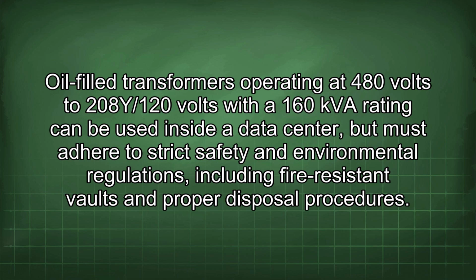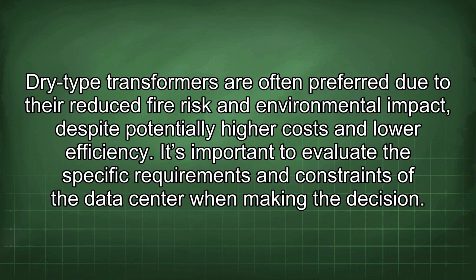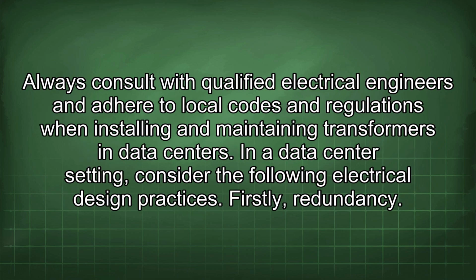Oil-filled transformers operating at 480 volts to 208Y/120 volts with a 160 kVA rating can be used inside a data center, but must adhere to strict safety and environmental regulations, including fire-resistant vaults and proper disposal procedures. Dry-type transformers are often preferred due to their reduced fire risk and environmental impact, despite potentially higher costs and lower efficiency. It's important to evaluate the specific requirements and constraints of the data center when making the decision. Always consult with qualified electrical engineers and adhere to local codes and regulations when installing and maintaining transformers in data centers.